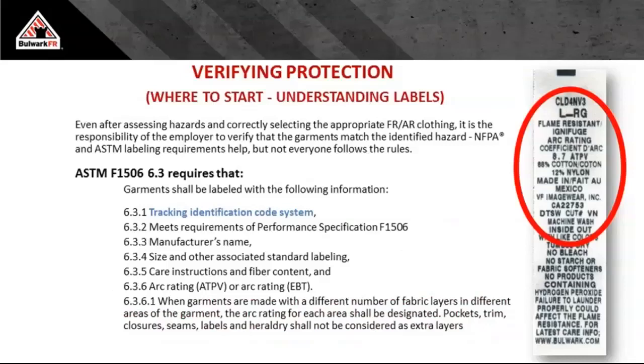Verifying protection. So we've talked about, okay, we're done. Derek, how do I know that I'm getting the right stuff? Well, the first place to start, and with a little bit of information, you can understand and decode labels relatively quickly. You have a lot of labels on your arc-rated FR clothing. Why? We are required to give you a lot of information. 1506 for us on the arc side, we have to follow all this on here. We have to tell you where it was made, when it was made, how and what it's made of, how much protection you have, and then we have to code it so that we can track it.